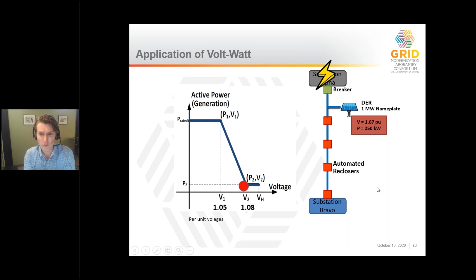And then thinking about stacking these functions, the Volt-VAR function is best suited for day in and day out operation of helping affect the voltage. It's unlikely to be able to really actively manage the voltage, but by controlling reactive power, it can contribute and affect that voltage locally and help reduce overvoltages and avoid potential mitigations that might otherwise be needed. On the other hand, Volt-Watt is really reserved for abnormal system voltages to act as that sort of soft shutdown. Next slide, please.